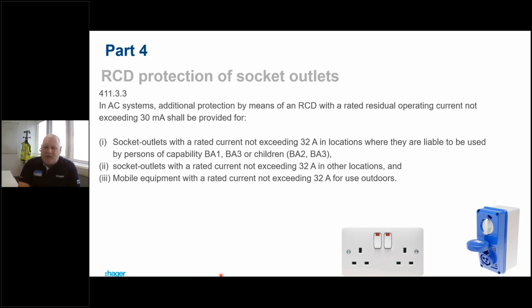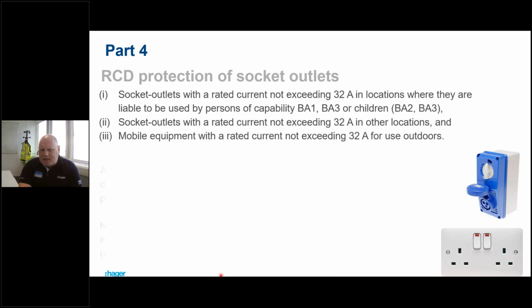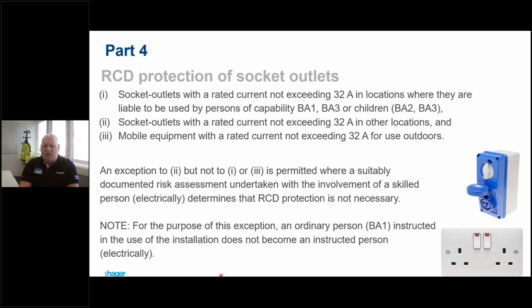That went with the 18th edition Amendment 1. Okay. Then we got the ability to use a risk assessment to risk assess out that need for an RCD. So that could be used in certain situations. So what do we do now? Okay, well, we still got the ability, okay, to have a risk assessment, but we can only apply that risk assessment to our indent 2 of the regulation.